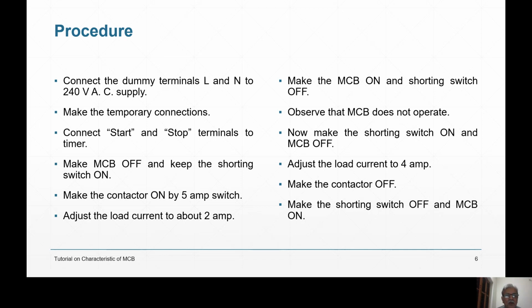Make the contactor on by the switch and then adjust the load current to 2 ampere. Our MCB is 2 ampere and we are adjusting the current to 2 ampere. We know that the MCB should not operate, and that is what we want to confirm. We will wait for 5, 10, 15 minutes and we will see that the MCB does not trip for 2 amperes. But now try to understand: you are passing 2 ampere through the MCB for 15 minutes, 20 minutes, half an hour, 1 hour, 4 hours, or 1 day, because in industry you are passing it for the complete 365 days and 24 hours.